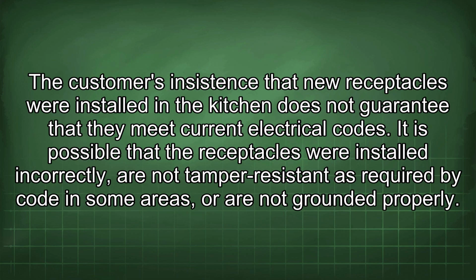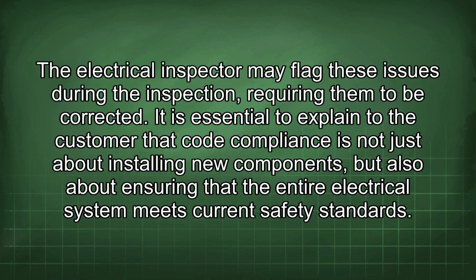The customer's insistence that new receptacles were installed in the kitchen does not guarantee that they meet current electrical codes. It is possible that the receptacles were installed incorrectly, are not tamper-resistant as required by code in some areas, or are not grounded properly. The electrical inspector may flag these issues during the inspection, requiring them to be corrected. It is essential to explain to the customer that code compliance is not just about installing new components, but also about ensuring that the entire electrical system meets current safety standards.